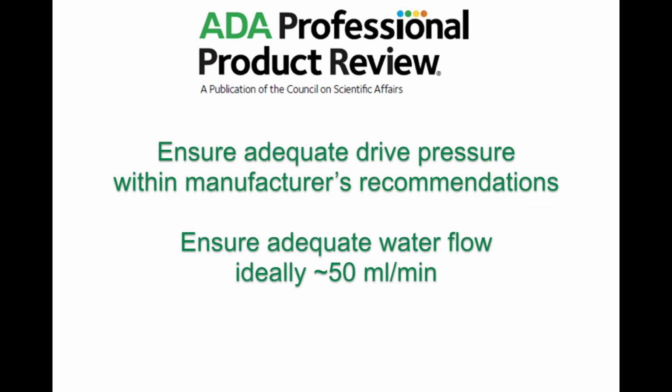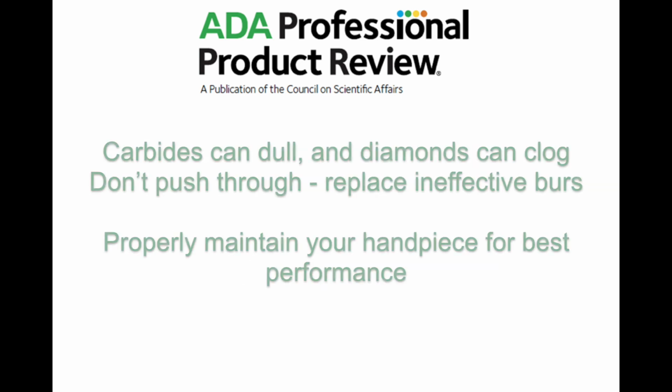If you're still not getting the performance you want, check your drive pressure, water spray flow rate, which should be approximately 50 milliliters per minute, and cutting instrument. And remember, proper maintenance is critical for getting the most out of your handpiece.